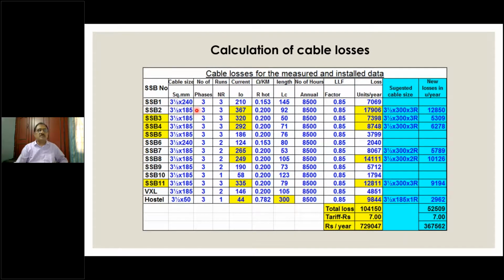So they chose 3 runs, 2 runs of 185 square mm mostly. And the losses, based on the formula which I mentioned to you, the resistance can be taken from the catalog. We worked out and found that the losses are like this. And if we suggested change in cable sizes, the reduction in losses is like this. So almost 50% reduction is available in the network by choosing cables of larger size.